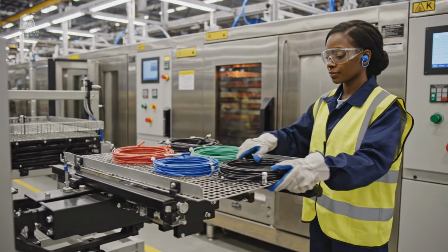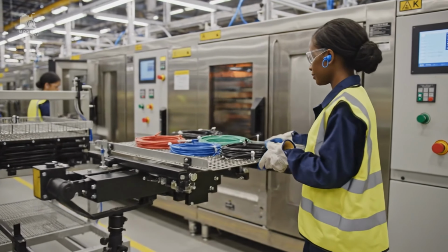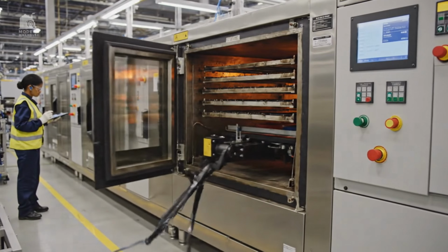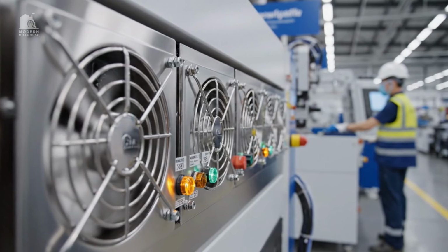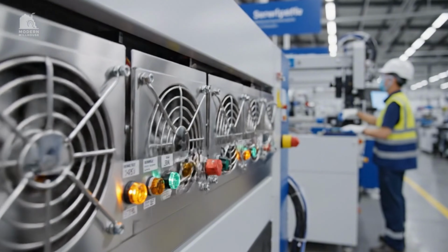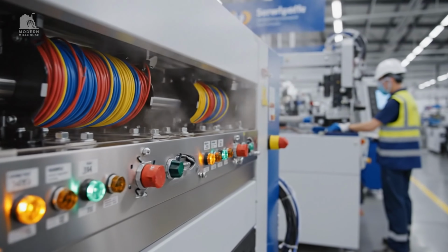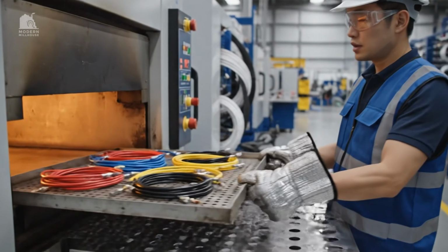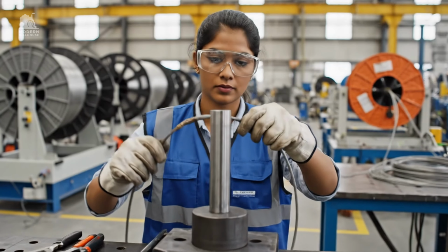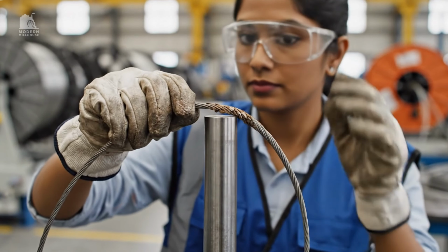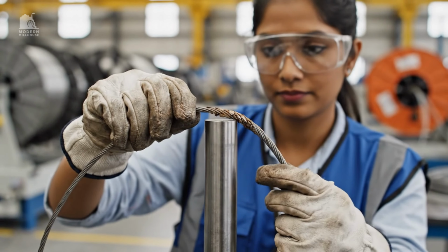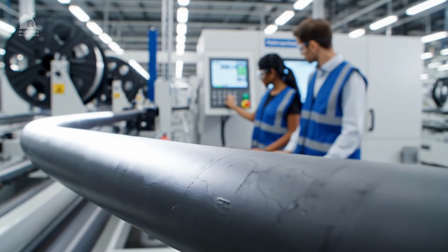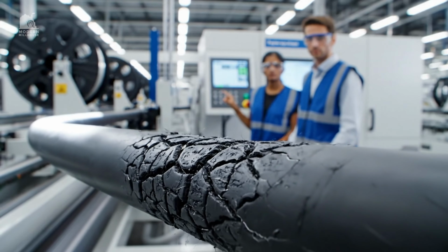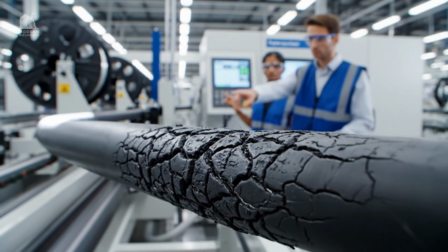Heat aging exposes insulation to high temperatures for set periods, simulating long-term service. Stable oven temperature matters. Small swings can change how polymers age and embrittle. After aging, the real question is hidden. Has flexibility dropped? And has strength degraded? Bending after heat can reveal micro cracks that aren't visible until the insulation is stressed. Aged cracking indicates the compound or extrusion conditions were wrong, and that batch can't ship.